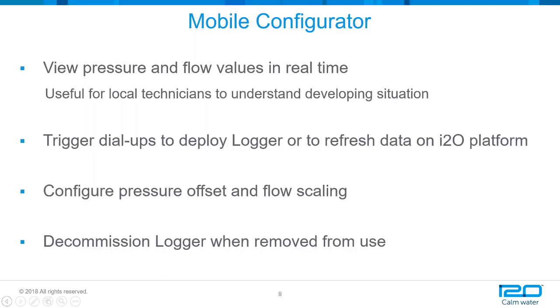But we can also deploy loggers using the mobile configurator. We can trigger dial-ups to deploy the logger or to get new data into the i2O platform. And we can also do the usual configuration things, like configuring a pressure offset or flow scaling to suit your flow meter on site.